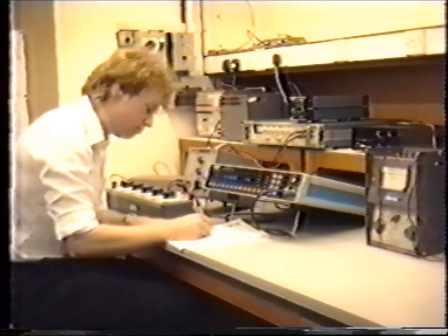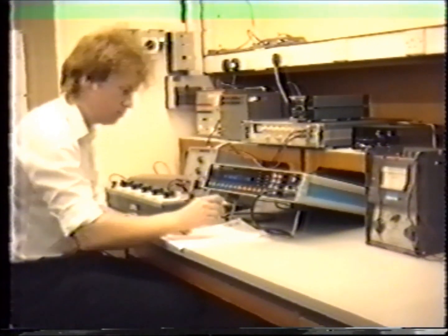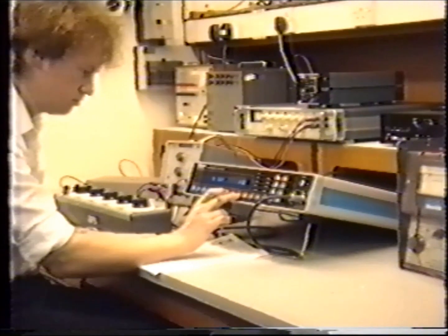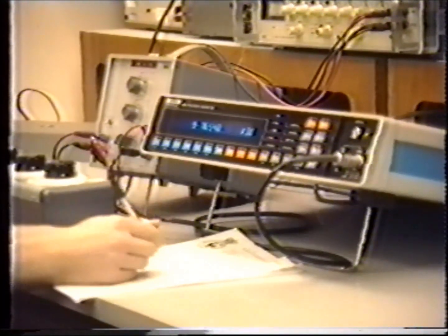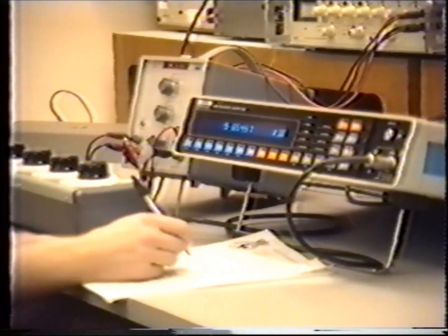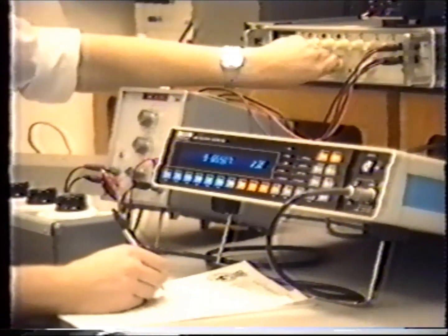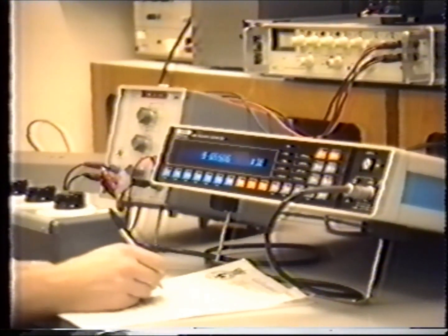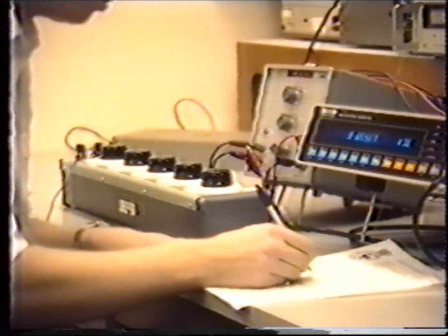Voltage sources, attenuators, and decade resistance boxes are calibrated using a Solartron 8.5-digit digital multimeter. The purchase of this highly accurate reference multimeter has simplified this area of calibration considerably. The purchase of much of the new electrical test equipment seen, together with the introduction of the MOTEX outstation calibration scheme, has cut the total workload considerably and, it is hoped, provided an efficient service to our customers.